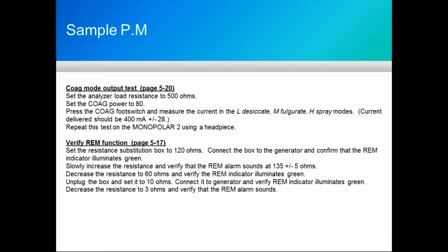For the coag mode, you set the resistance to 500 and the coag power to 80. You run through all the modes. The mA should be 400 plus or minus 28. Then you repeat the test on monopolar 2 using the handpiece. For the REM function on page 517, you use your tester and set it at 120 ohms. Then you run through a series of tests looking for the green light and making sure that it will go back to green. I'm sure all of you have done all this quite a few times.